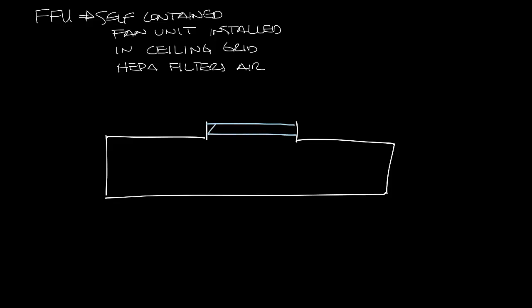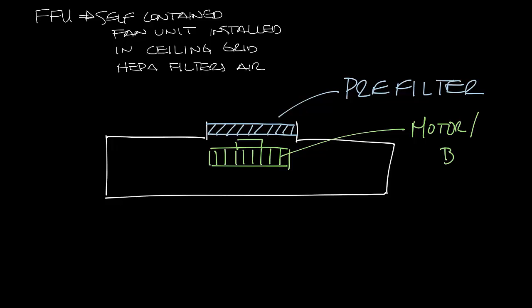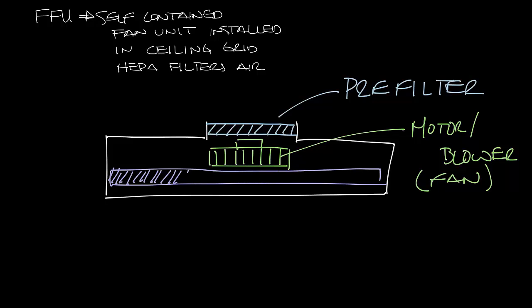There's often a pre-filter at this inlet and then a fan and motor assembly below that, that boosts the air through the filter, and then below that is the HEPA filter.